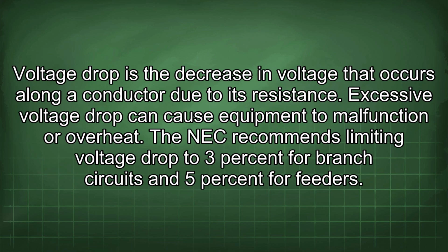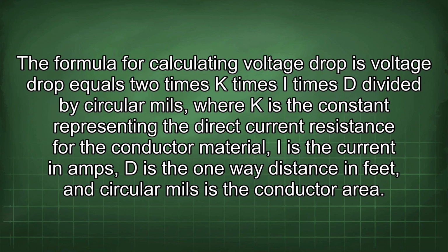Voltage drop is the decrease in voltage that occurs along a conductor due to its resistance. Excessive voltage drop can cause equipment to malfunction or overheat. The NEC recommends limiting voltage drop to 3% for branch circuits and 5% for feeders. The formula for calculating voltage drop is: voltage drop equals 2 times K times I times D divided by circular mils, where K is the constant representing the direct current resistance for the conductor material, I is the current in amps, D is the one-way distance in feet, and circular mils is the conductor area.